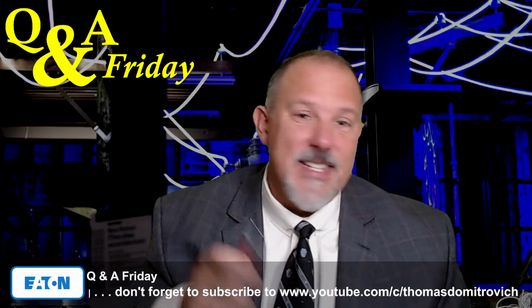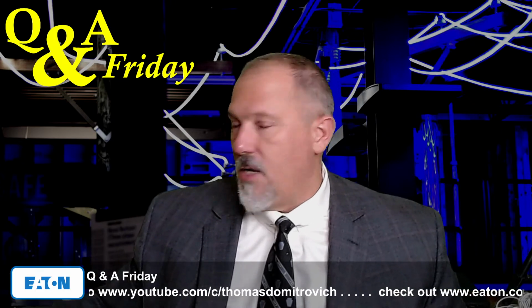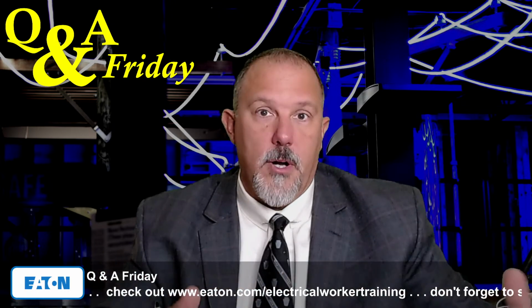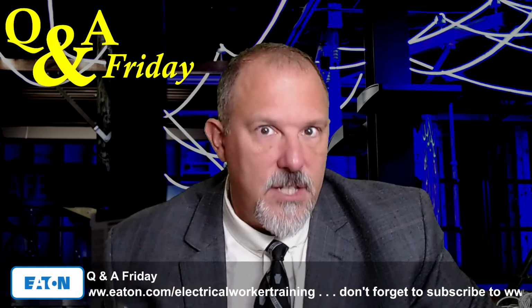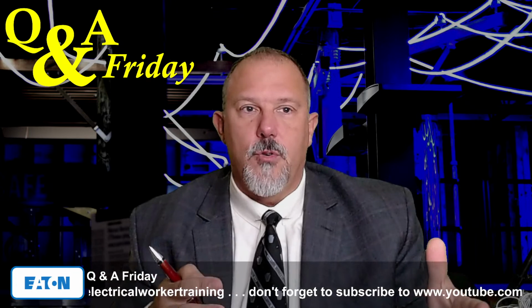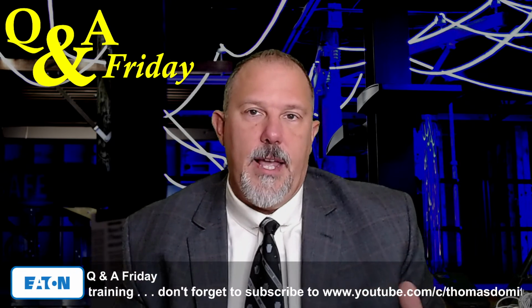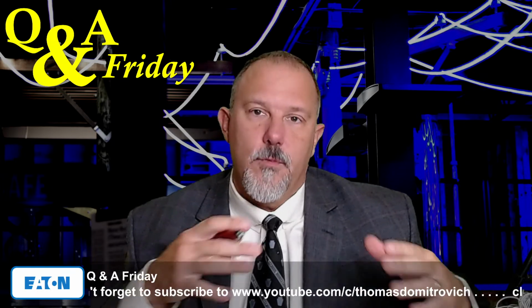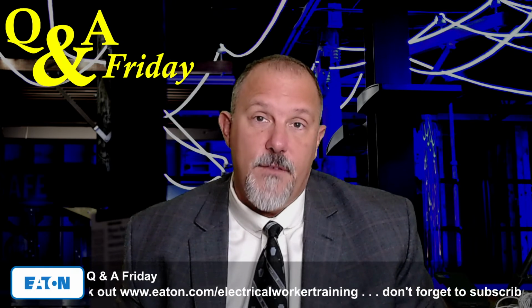Ooh. So this is an actual question, and I had a phone call with this gentleman, a great electrical inspector who's trying to help the contractor out and know whether he can approve something or not. In this case, they had a meter center that damaged one of the compartments, and I didn't have pictures of it, but he said the damage to that cubicle is very extensive. So you can't just say, hey, I'm going to brush it off and be back up and running. They'd have to reconstruct one portion of the meter center. And so he said, how do I address this? What do I use as a reference to say whether I can or cannot fix this up?